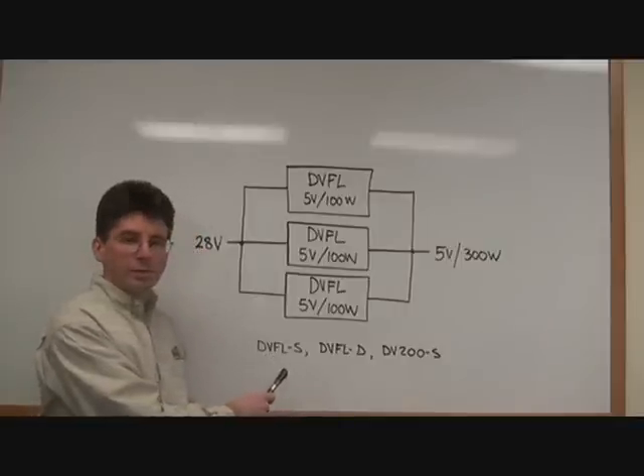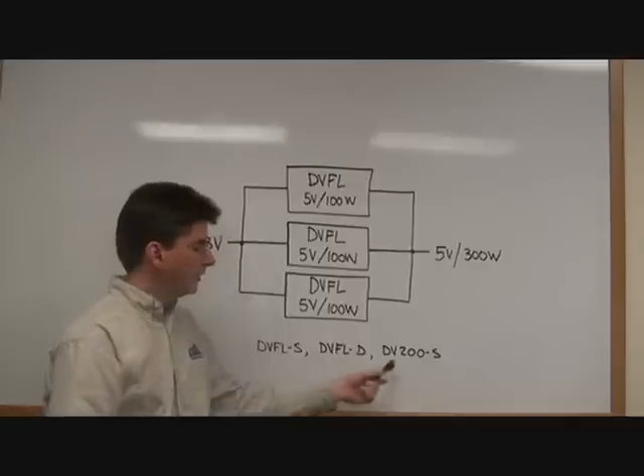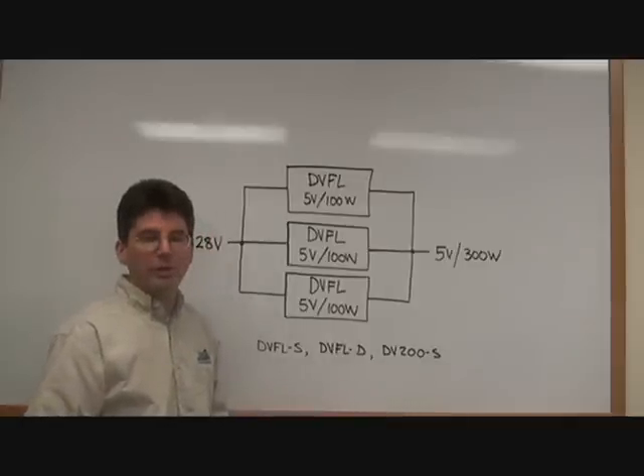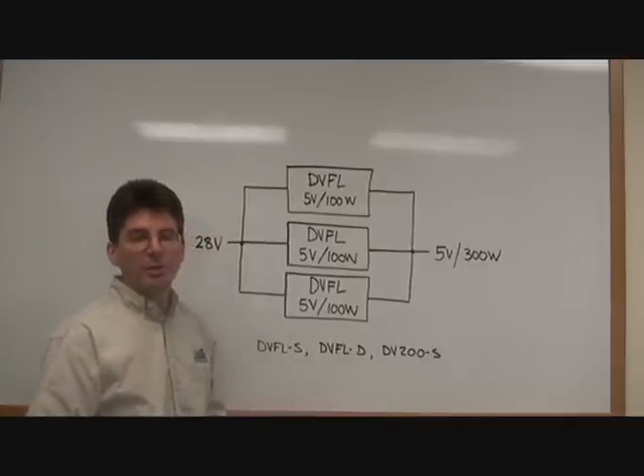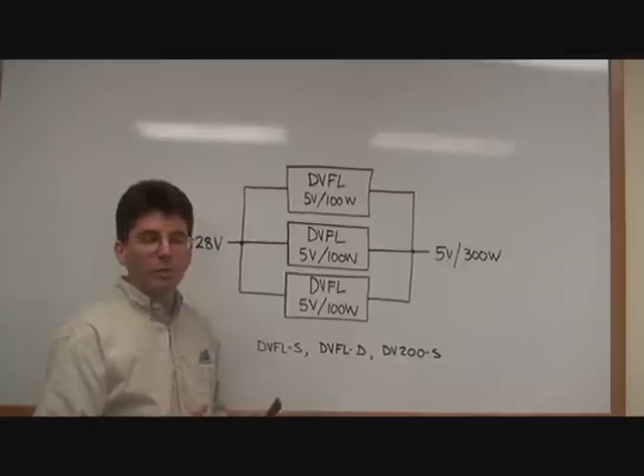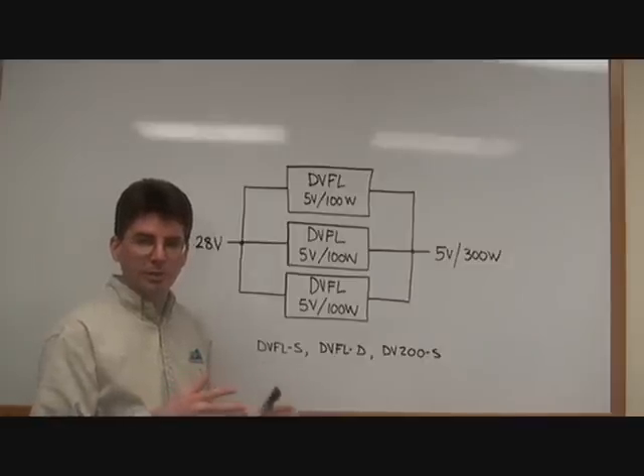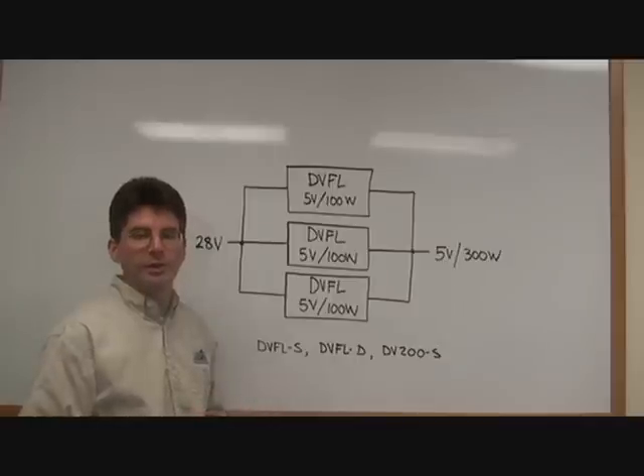The following models, DVFL single, DVFL dual, and DV200 single, offer current sharing capability. The current sharing capability is a single wire connection between models which enables them to share the load or split the load equally among different DC-DC converters.